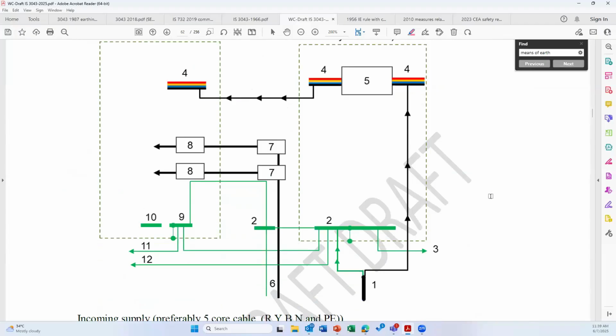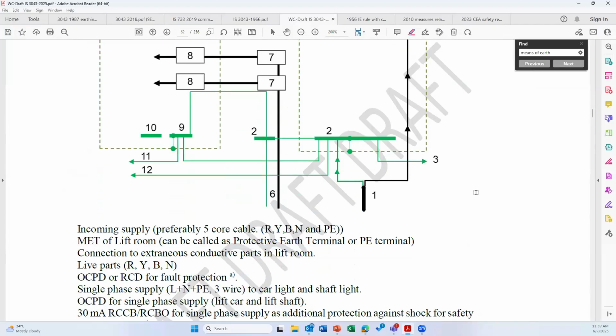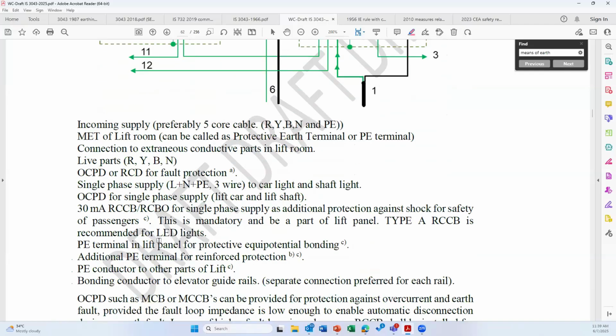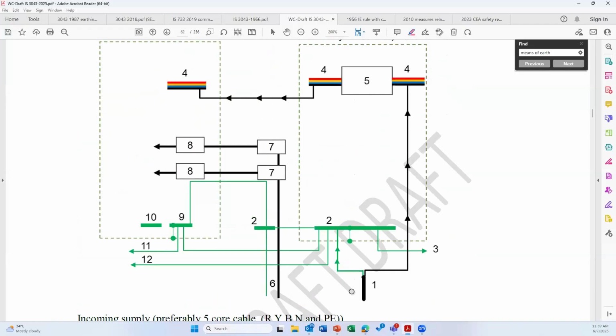Lift. A new picture has been made and put in the lift, but unfortunately the automatic numbering has been missed in the key, so you have to read this as serial number 1, 2, 3, 4. So this was a small error which has happened. What do we do in case of a lift? This box, this dotted line, this is the lift panel. The lift panel is getting a supply from the mains. The earth bus bar is connected to a common earth bus bar, serial number 2. This is the earth bus bar in the lift panel.